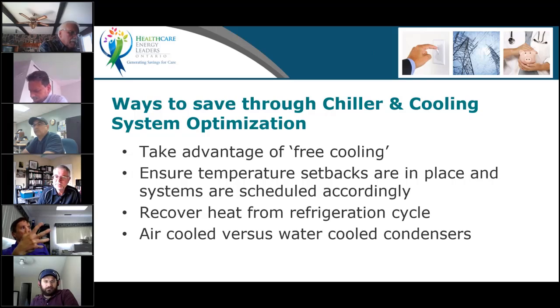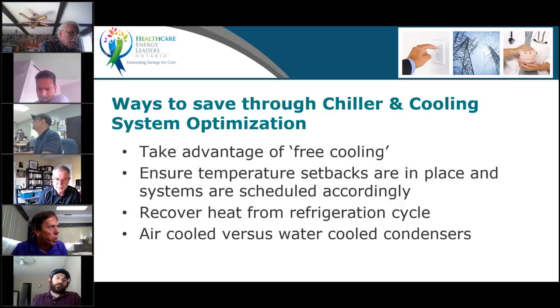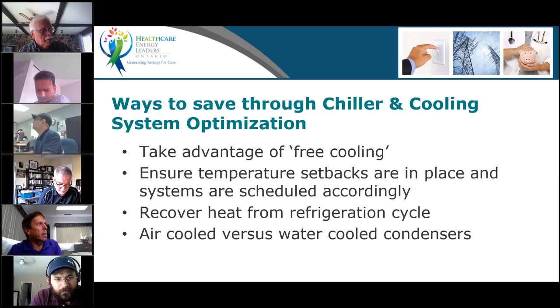Obviously, when you have a chiller plant, you want to take advantage of free cooling. I talked about that in the previous section. When you talk about free cooling, you've got two main types: air side free cooling, with your economizer on your air handling unit, and water side free cooling, where you use a plate heat exchanger, typically with your cooling tower. Depending on the type of chiller plant you have and the type of humidification you have, you may go from free cooling using air side to free cooling using the water side.